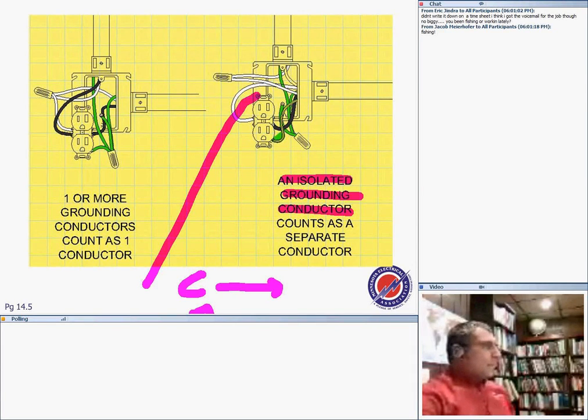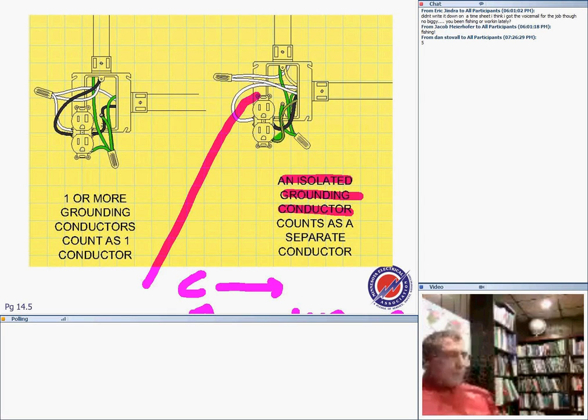Let's count for this box. Just not the receptacle yet. Let me make it easy for you. For a receptacle, I have one of them, and that counts as 2 conductors. So that's 2 for the receptacles. That's easy. Now the conductors that count.